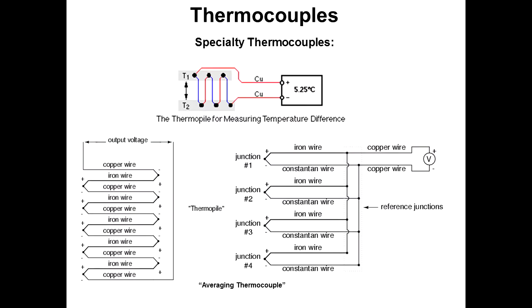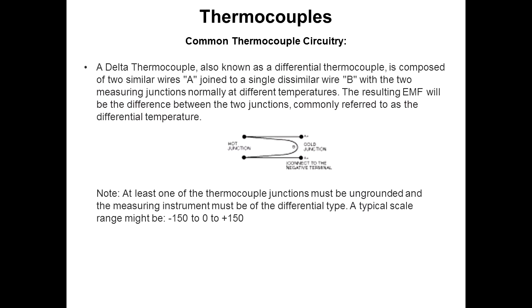More of these same things: differential temperatures, where you have thermocouples connected in series, and you have your copper wires going from one end to the other. That's where your cold junction is, where the copper wires are connected to the thermocouples, and it's important that the copper wires, the red wires going back to the reference thermometer, are all kept at the same temperature along those wires. And more pictures of averaging thermocouples. It's the wiring diagram. So a differential thermocouple is where you have two wires of the same material for your outer wires, then you have a different material that's connecting the two of them, and you have to have a special instrument that will read the differential. So this gives a differential temperature between the two hot junctions.